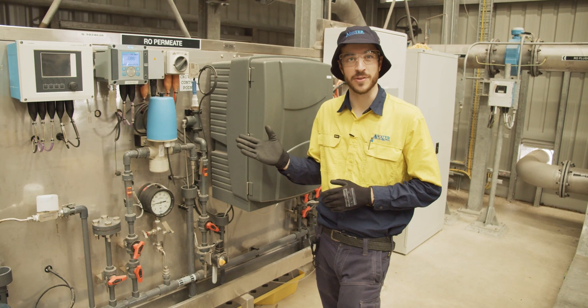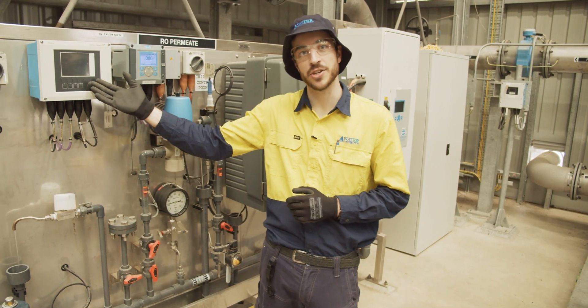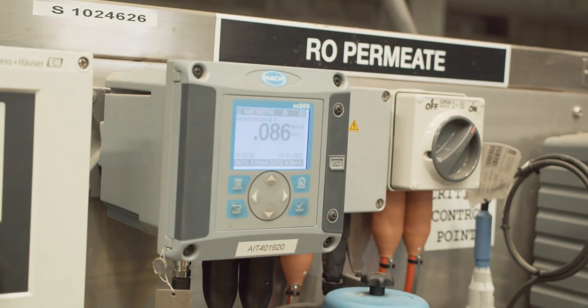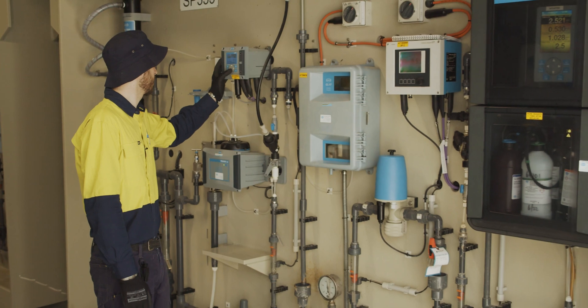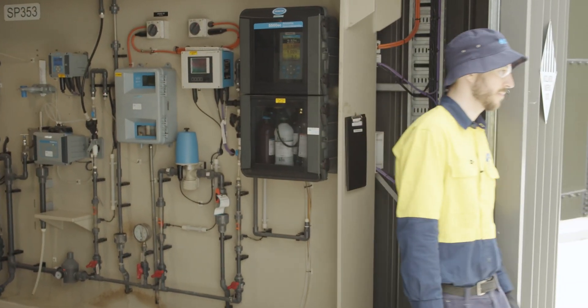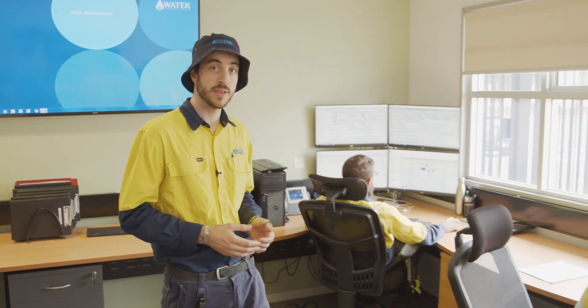This is one of the many sample panels around the plant. They measure different aspects of water quality, such as pH and conductivity. If the water doesn't meet the standard at a particular checkpoint, it triggers an alert for us to take action, which may mean diverting the water until the required water quality is achieved. That's very rare — most of the time, it's all smooth sailing here in the plant central control room.